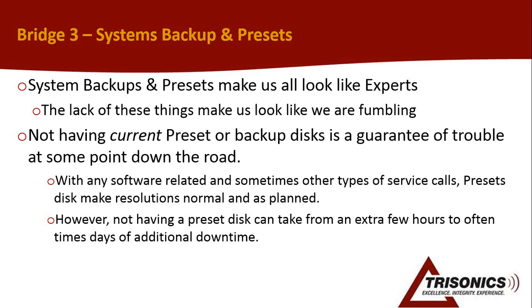And this isn't the kind of thing that we run into every now and then. I run into this on a pretty consistent basis. Usually 3-4 times a year, I have a situation where I get called in on a machine I've never worked on before, and there is no preset disk. Either there was one once and it disappeared, or no one had made one, or the one that's there is 5 years old and everything has changed. So it doesn't really provide a tremendous amount of help. And when that happens, the recreation time of all of that information is easily extra hours.